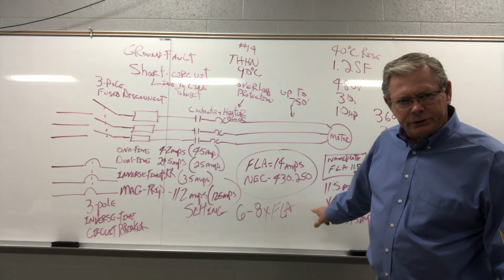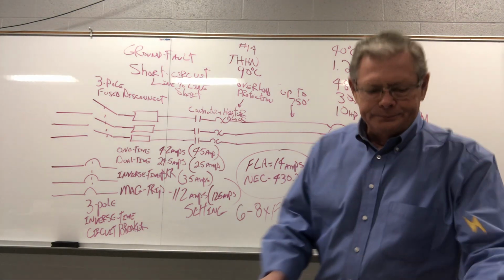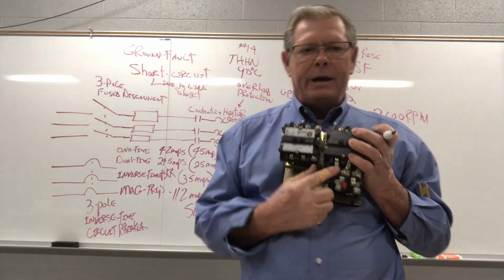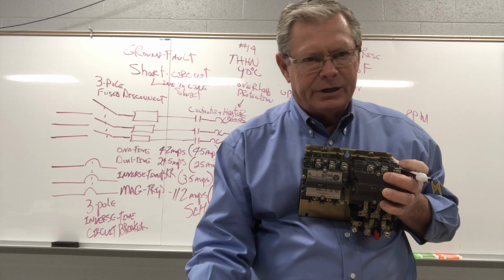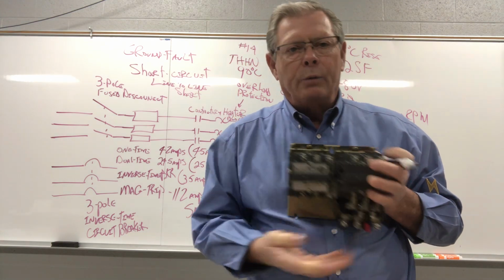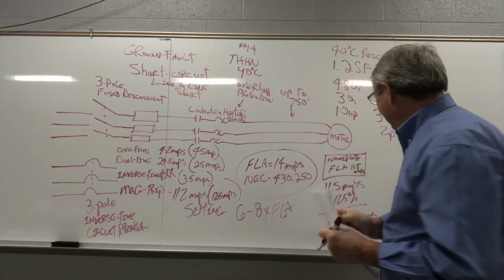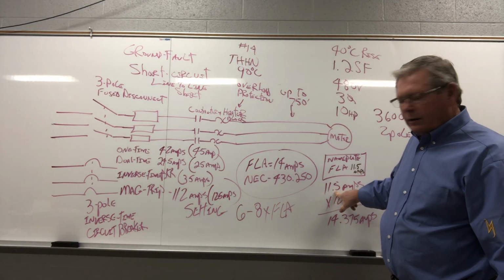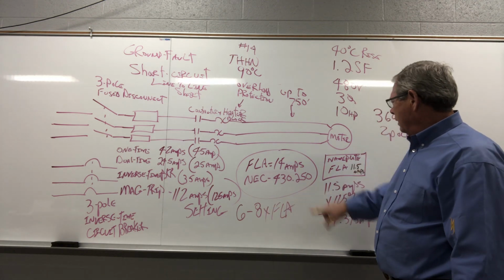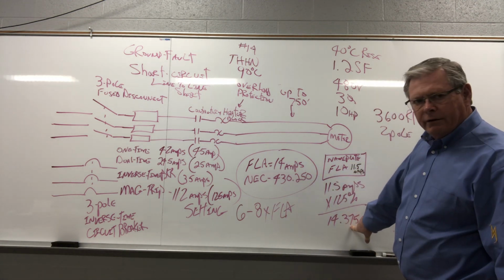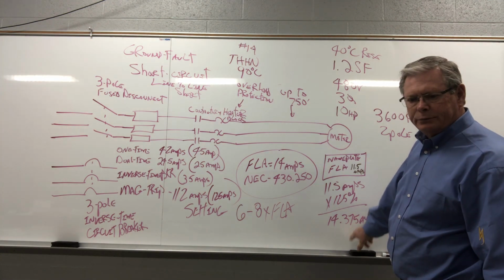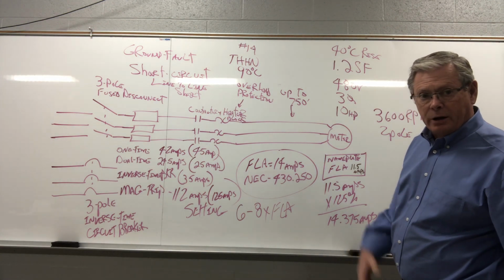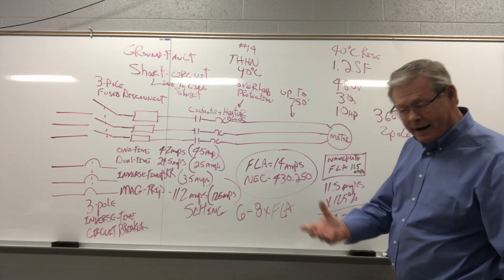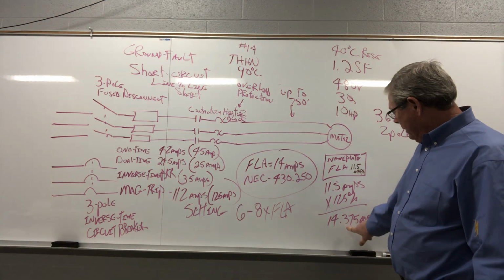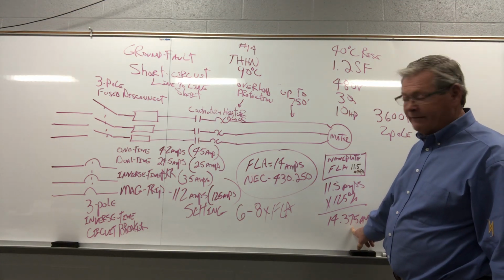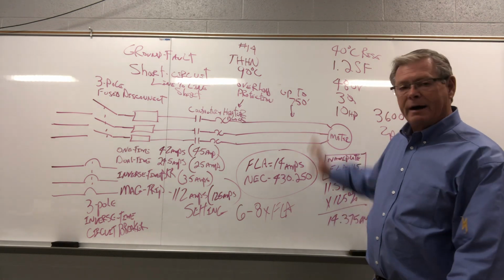If we know this as electricians, and we look at that starter right here, and we get those numbers, and we look it up on a chart, you gotta have a heater chart, not getting into that right now, and we see that this motor had 11.5 amp heaters in it, we could calculate that here for 14.375 amps, change those heaters out because it was tripping out because they're trying to pump stuff that's too heavy or heavier than they normally pump. We can bump those heaters up to 14.375 amps and it may run just fine. And you still have motor protection.